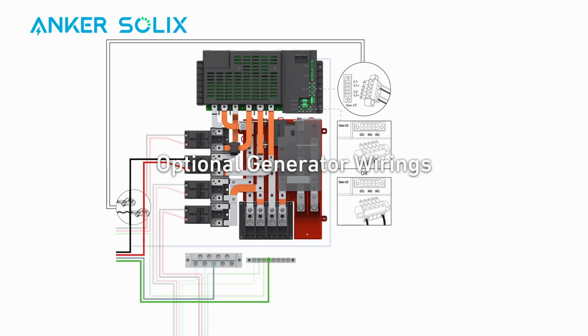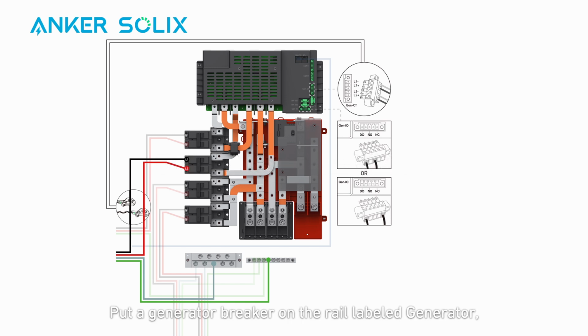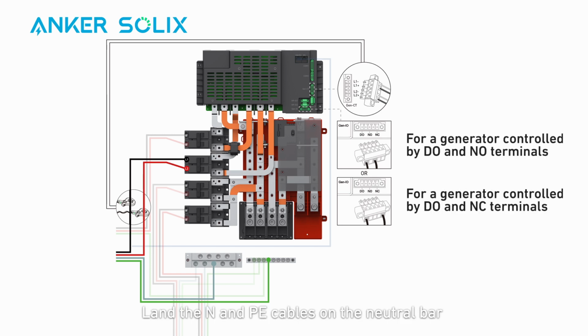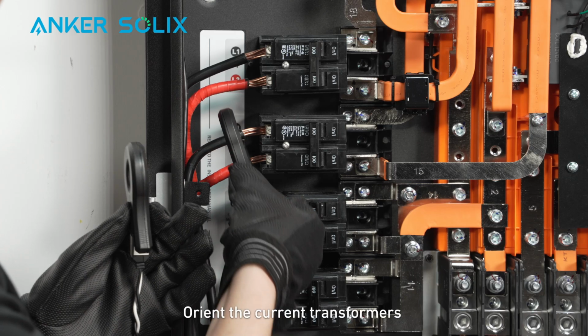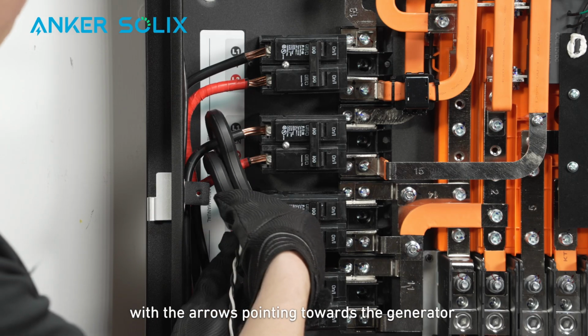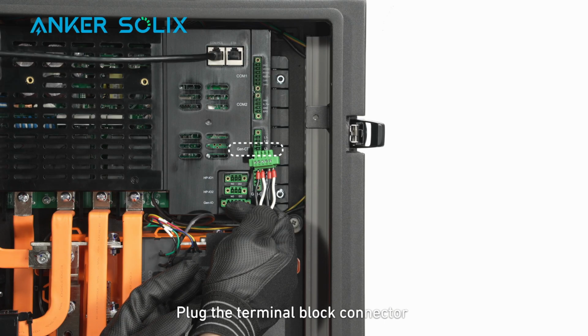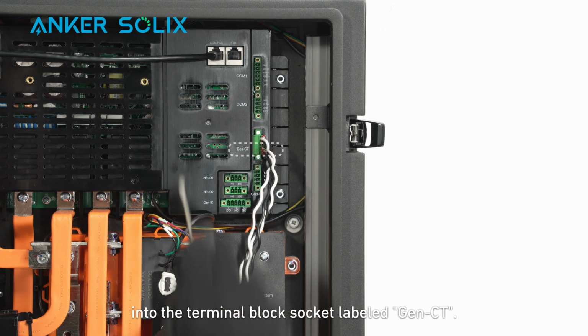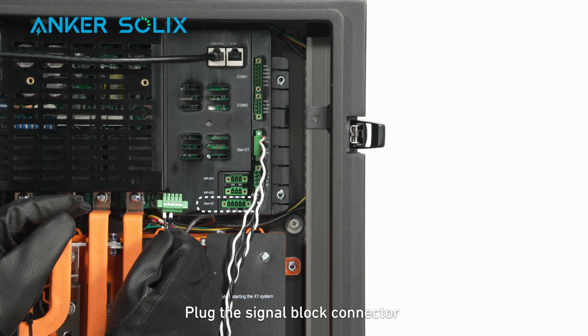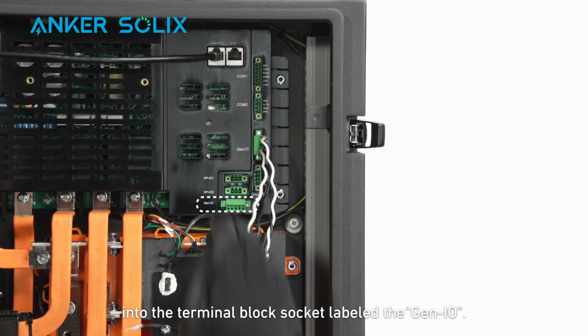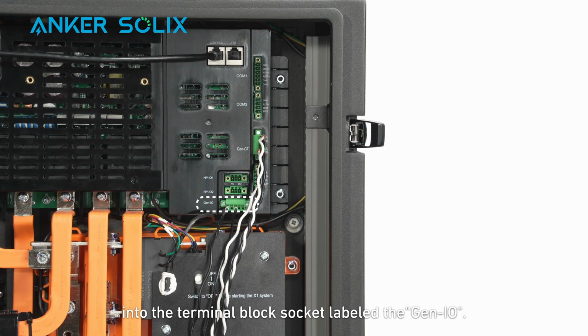Generator wirings, optional. Put a generator breaker on the rail labeled generator, and then secure the breaker using M3 screw. Land the N and PE cables on the neutral bar and ground bar respectively. Connect the L1 and L2 cables to the L1 and L2 poles of the generator breaker. Orient the current transformers with the arrows pointing towards the generator. Plug the terminal block connector into the terminal block socket labeled Gen-CT. Plug the signal block connector into the terminal block socket labeled Gen-IO.